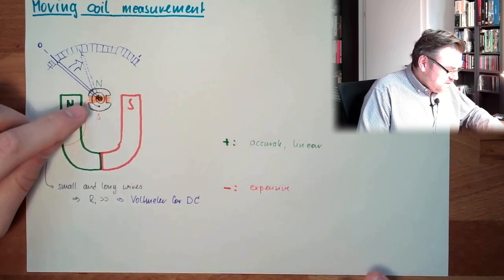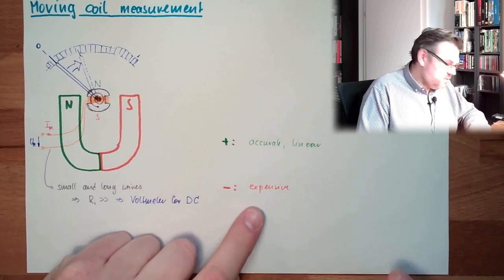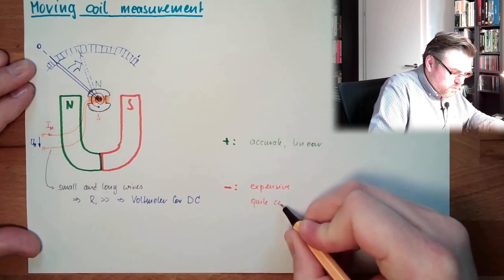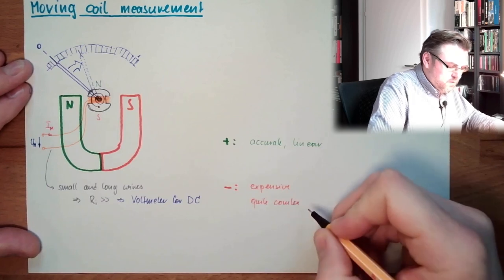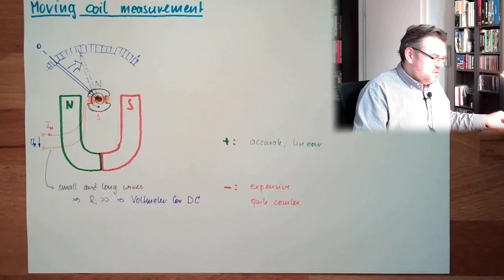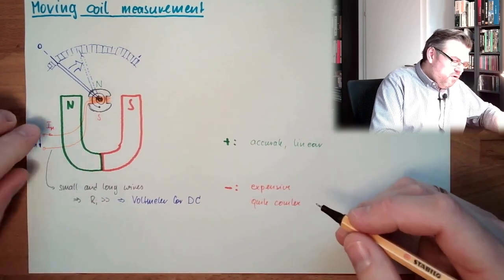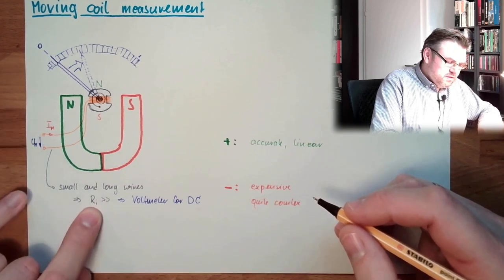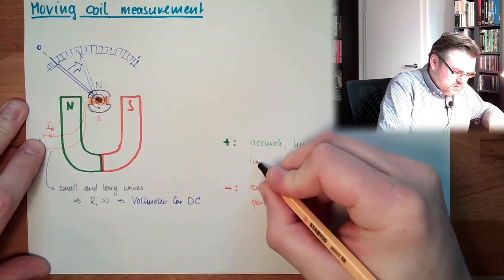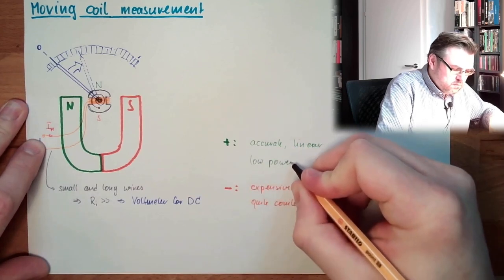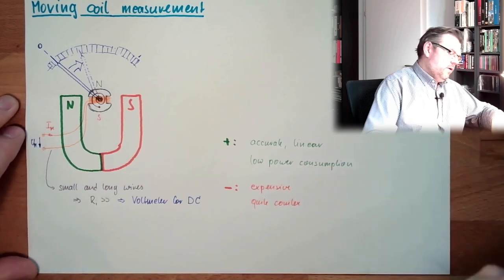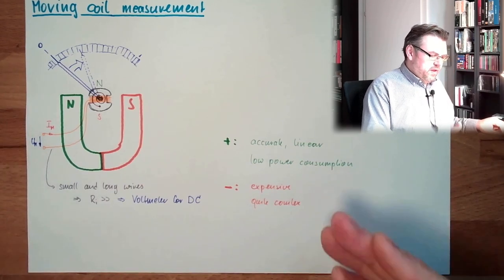One downside on the other hand is it is expensive. So we have an expensive measurement device, which is however pretty accurate and linear. And because this is a long coil, it makes it expensive. It's also quite complex. It's quite complex because of this, you have to deal somehow with the movement and the springs. However, we have a very low power consumption because the measurement voltage, you know, it's a big resistance and low power consumption.